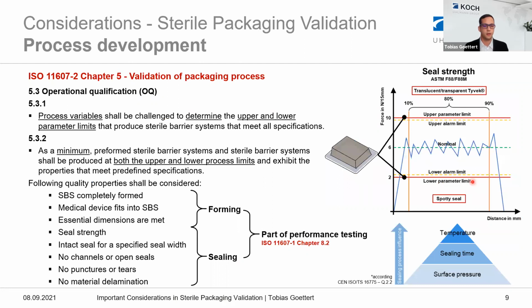So sorry about this overloaded slide, but I will summarize it for you. So we are at our first step, the process development. This means to define your parameters. Therefore, we are now at the ISO 11607, which means the validation for the packaging process. And it says in the OQ, or during the operational qualification, you have to determine your upper and lower limits for your process variables. This means in our specific case about the seal strength, you have to define an upper, in this case, or in this example, a peeling force from 2 to 10 newtons per 15 millimeter sample width.